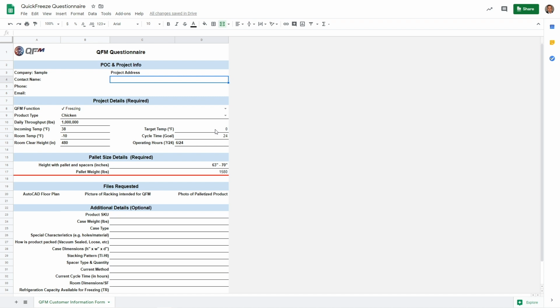So this customer wants to be able to turn every freezing location within 24 hours. And then we look at how many operating days and hours, which can have an effect on how many positions we recommend. And then the last bit of information above the red line is the anticipated height of the product with spacers. So we include the pallet, the product, and the spacers. In this example, we're running a range of 63 to 70 inches on pallet height. Next, we get information from the producer on average pallet weight. In this example, it's 1,580 pounds per pallet.